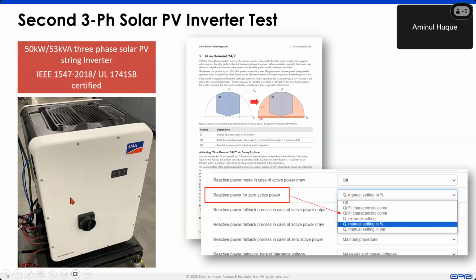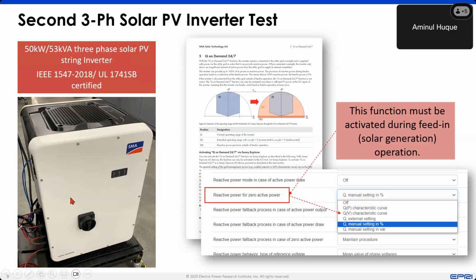I'm talking about 1547. And also in that mode, you can turn it off, which is the default, but you can also turn it on and then select which control mode needs to be operated. So we selected the QV, which is basically the volt-var function. But again, one thing I have to highlight: for both inverters that we tested, this setting has to be activated when the inverter is operating. So basically during daytime operation or the solar generation period, you have to activate it, and that will continue to operate. If not, it will go to sleep mode, the low irradiance condition equivalent to sun nighttime.